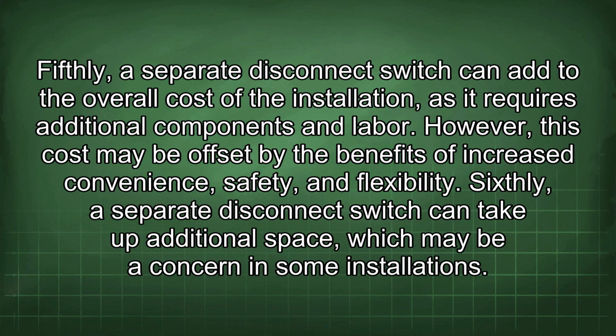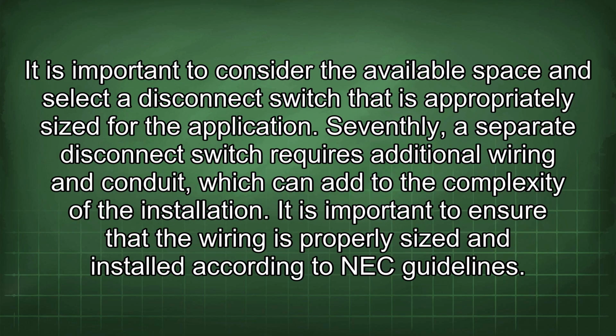Fifthly, a separate disconnect switch can add to the overall cost of the installation as it requires additional components and labor. However, this cost may be offset by the benefits of increased convenience, safety, and flexibility. Sixthly, a separate disconnect switch can take up additional space, which may be a concern in some installations. It is important to consider the available space and select a disconnect switch that is appropriately sized for the application. Seventhly, a separate disconnect switch requires additional wiring and conduit, which can add to the complexity of the installation. It is important to ensure that the wiring is properly sized and installed according to NEC guidelines.